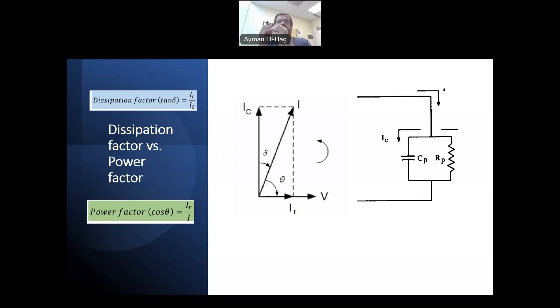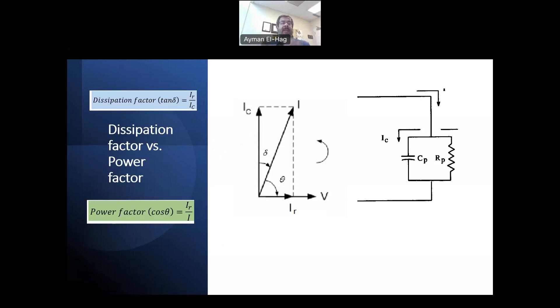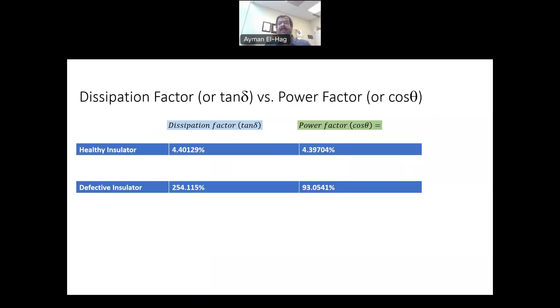Why is it that when the insulator is not defective, the dissipation factor and the power factor are very close to each other, and when it is defective, they are far away from each other? This would lead us to answer the big question: are the dissipation factor and the power factor the same thing, or are they two different things? Just to remind us about the results — for the healthy insulator, the dissipation factor was 4.4% and the power factor was 4.397%, very close to each other.